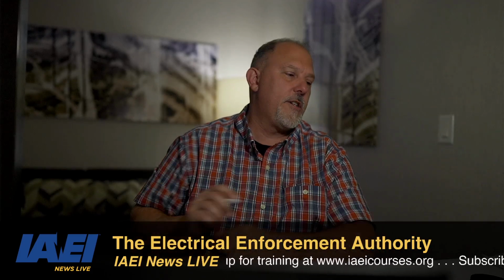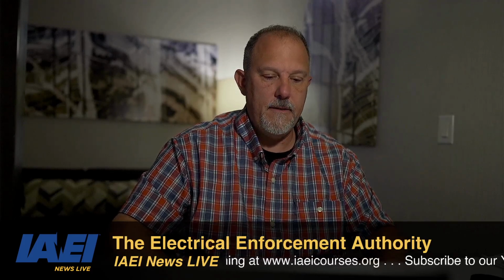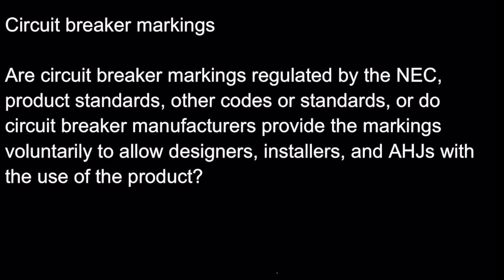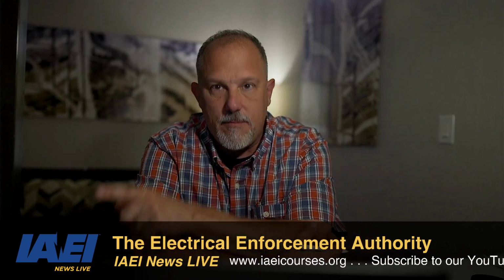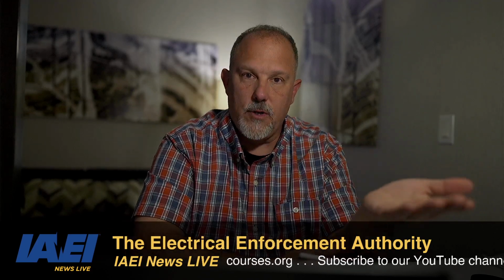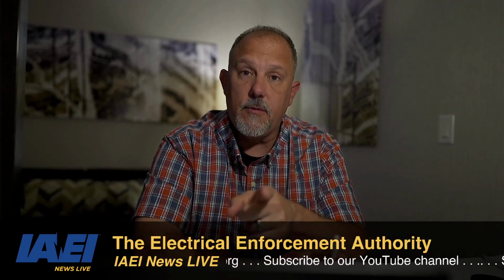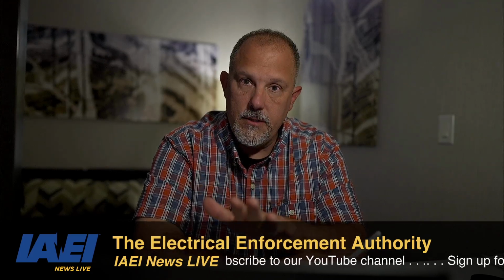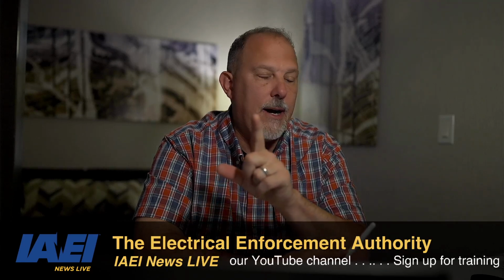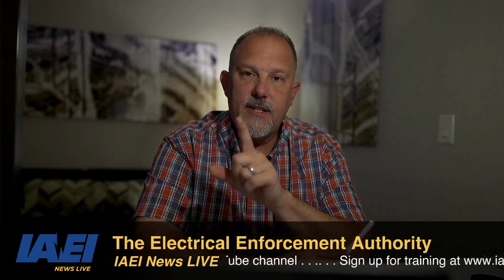So first question up. Let's put this up on the screen. First question: are circuit breaker markings regulated by the NEC, product standards, other codes or standards, or do circuit breaker manufacturers provide the markings voluntarily to allow designers, installers, and AHJs to use the product? Good question. The answer to that is that the standards are what drives the markings. You're not going to have a code requirement that drives all of the marking requirements. Now, there are some marking requirements in the NEC, but for the most part, your circuit breaker markings are identified in UL 489 and associated, or the appropriate standard, right?